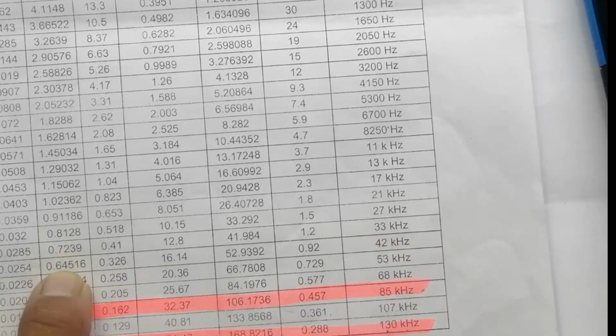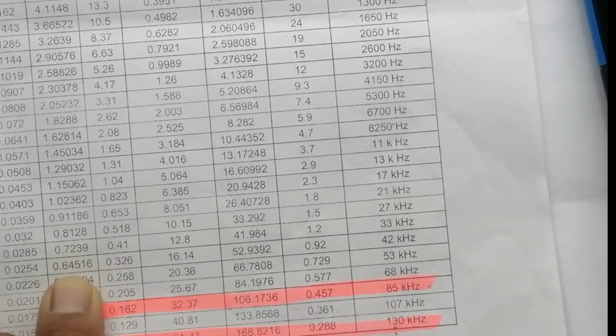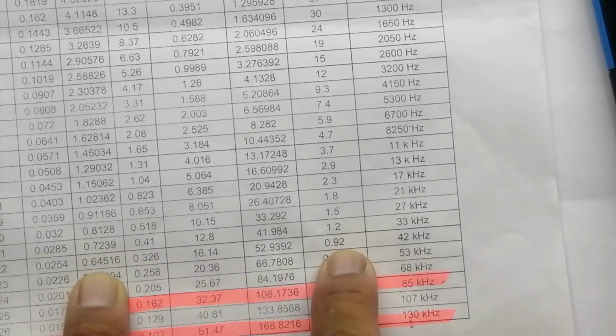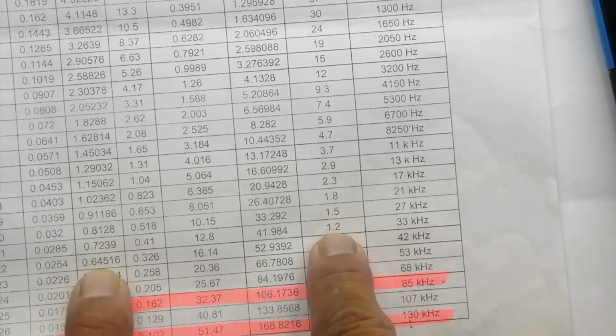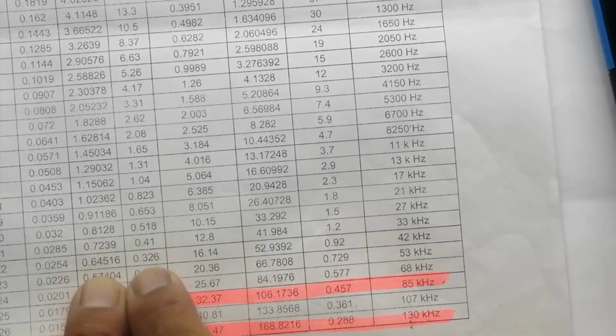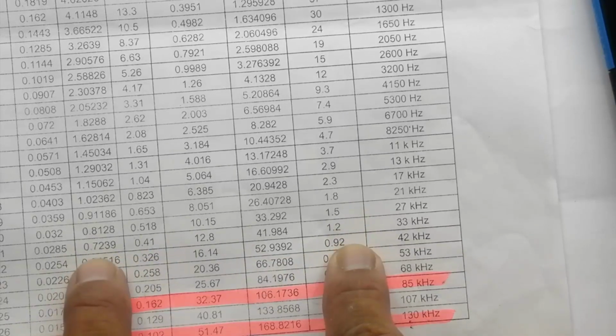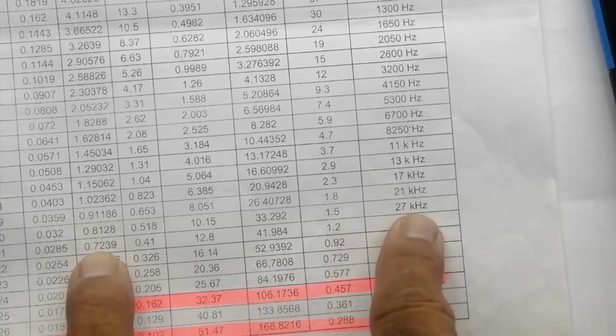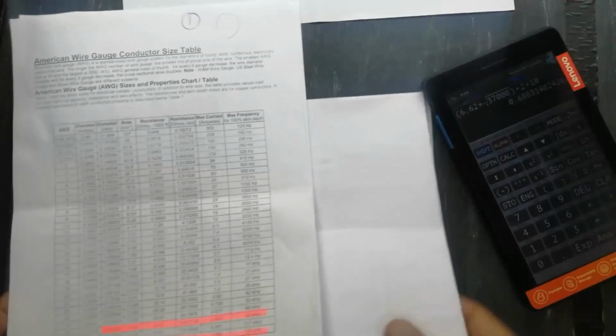Then you have to decide how much current you need. If we need within this range, then we use this wire. If our transformer needs primary or secondary current more than this, then we have to use this wire. So we have to choose by means of wire diameter, frequency and current.